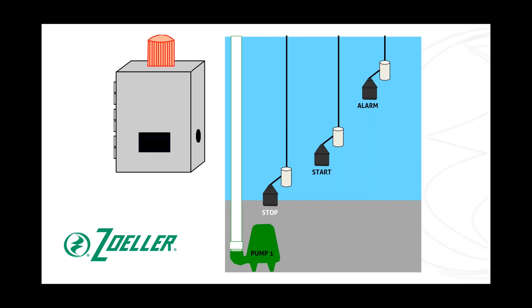I want to stop right here and just ask you, can you think of any common mistakes here, something that could go wrong? I'll tell you one is that when people put in a control panel and float switches, a lot of times they don't think it's important or don't take the time to mark the wires on the float switches. And if they mess up the order of those float switches, and as long as they don't get the alarm hooked up to the stop or the start switch, this panel is still going to operate, but it's not going to operate correctly.